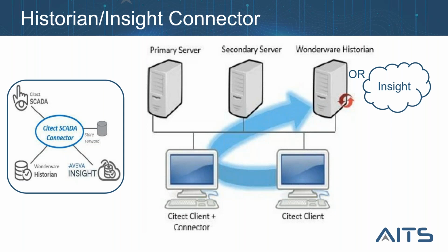It's also worth mentioning that it supports a store and forward feature. Whenever the connection between the Citect SCADA client and the connector is shut down, or the connection to the historian is shut down, it will start to store the data locally on that Citect runtime machine. Whenever the connection comes back online, it will automatically resume and forward the data to either the AVEVA Historian or AVEVA Insight. This store and forward feature is really nice.